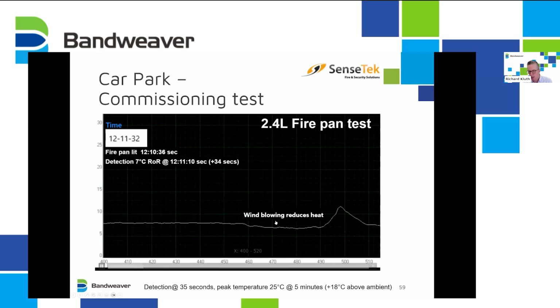In this case, you can see the wind actually starts reducing the fire. It's blowing it around. So you can see how small the fire is, that even a relatively small amount of wind can affect it. The fire builds back up, and so it peaks round about, I think, two minutes at 25 degrees C, we'll see here. So the absolute alarm would still never detect for this fire pan test. So the only chance you've got of detecting is with a rate of rise.